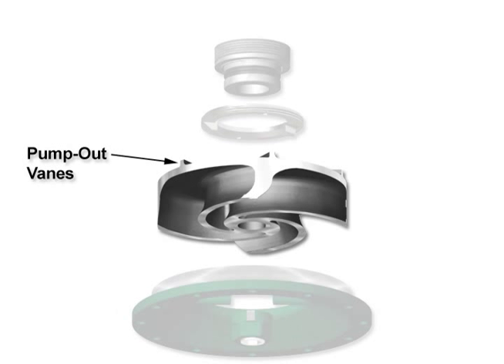Pump out vanes on the impeller backplate act to pump away stray solids around the seal area while offsetting thrust loading against the pump bearings.